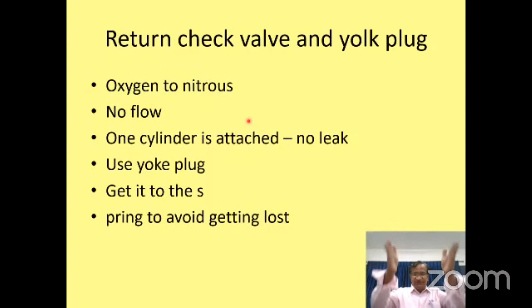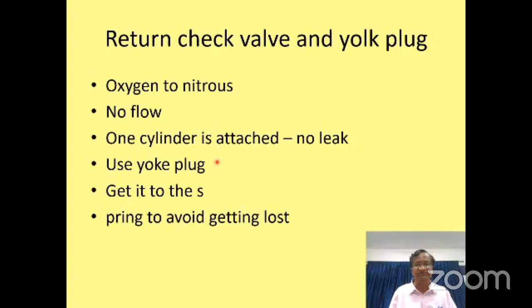Return check valve and yoke plug. Oxygen to nitrous: if you open the oxygen, will it go to nitrous? No, it will not go. No flow. If one cylinder is attached, no leak. Use the yoke plug. Now we have 2 cylinders. If one cylinder is open, in the other there is no cylinder at all. The port is open to the atmosphere. There we need to plug with the yoke plug because sometimes, rarely, we can have some leak. Yes, we may need to plug the yoke plug here, and I think that adapter is missing.